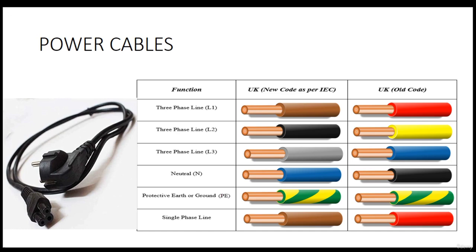Power cables. In addition to the importance of good installation of power cable from the main source till the socket outlet for the IT cabinet racks, the color code for cables is very important for the following reasons. 1. Avoid faulty connection during installation between the rack plugs and socket outlet, which will cause damage to the rack devices in case they are connected to PDUs that are not acceptable, which can make a huge mistake. 2.